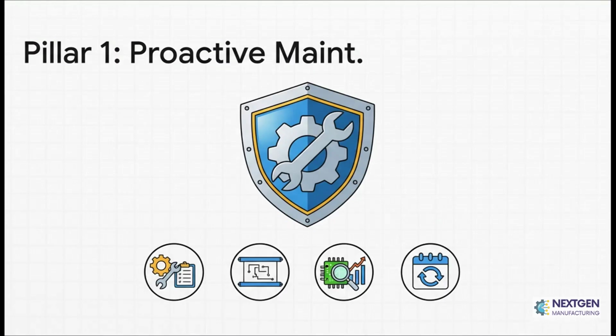So, pillar 1 is proactive maintenance. Safety begins long before anyone even picks up a tool. This means having accurate single-line diagrams, basically your electrical roadmaps, and doing the studies to know what the potential fault current is. That's the maximum energy the system can unleash in a short circuit. Regular maintenance and audits prevent failures before they even have a chance to happen.